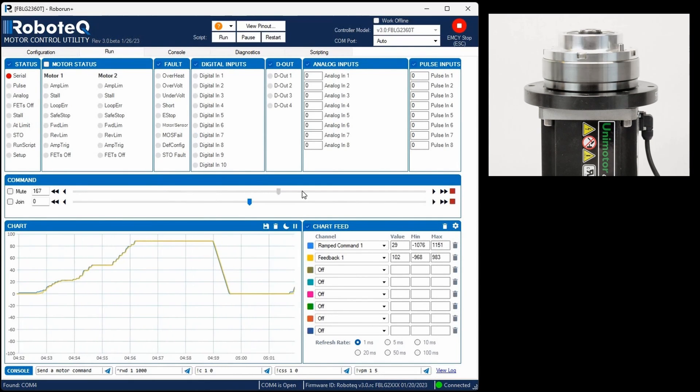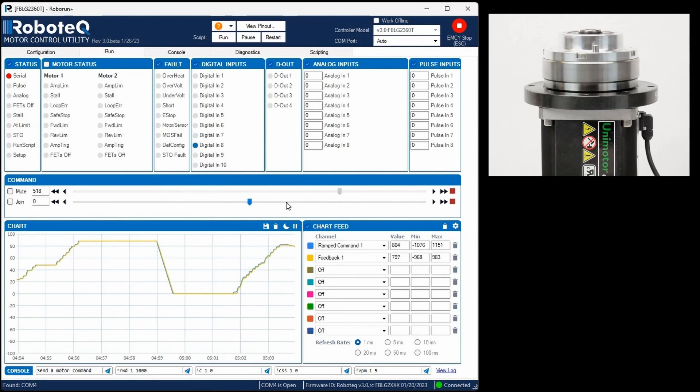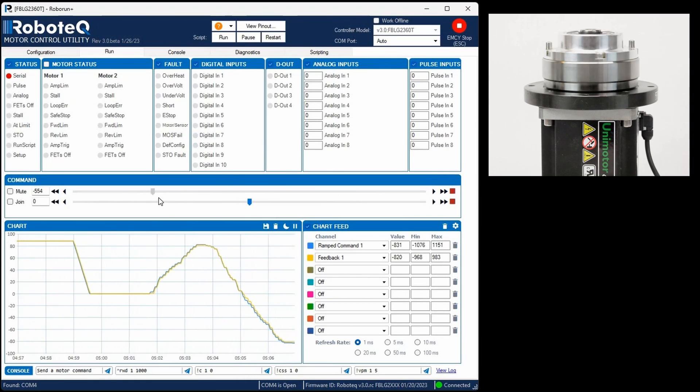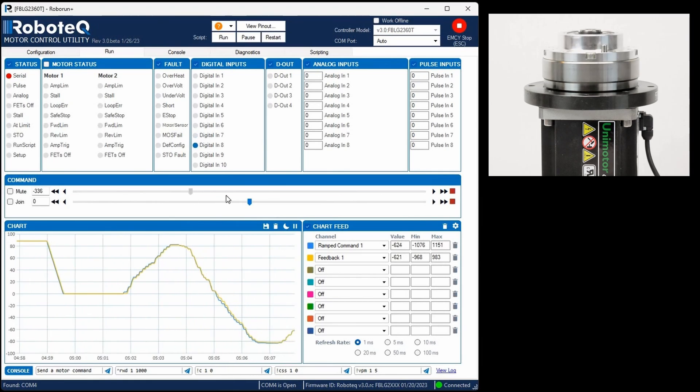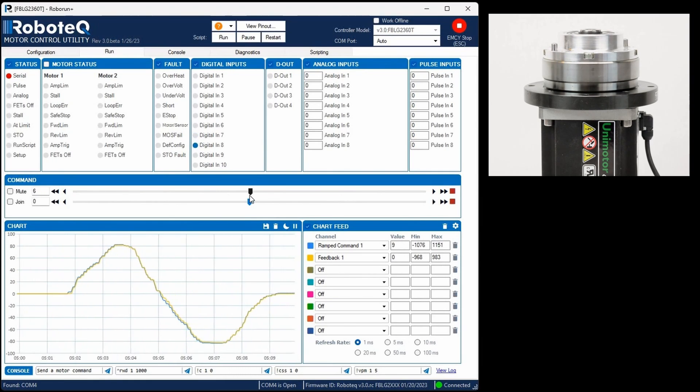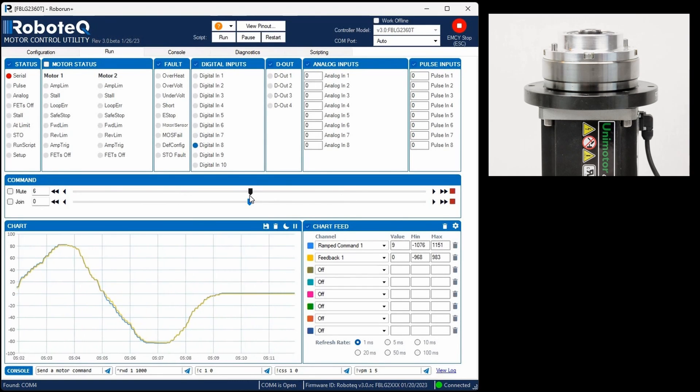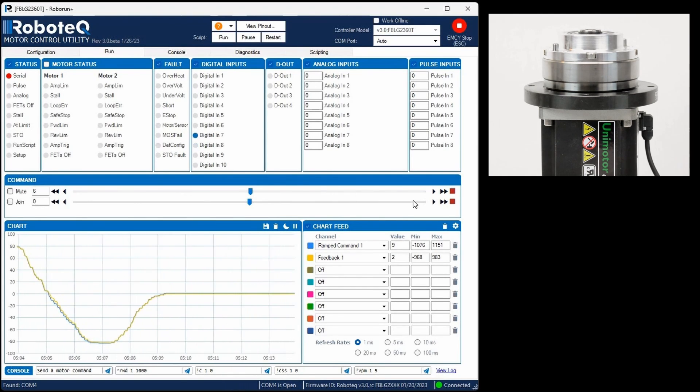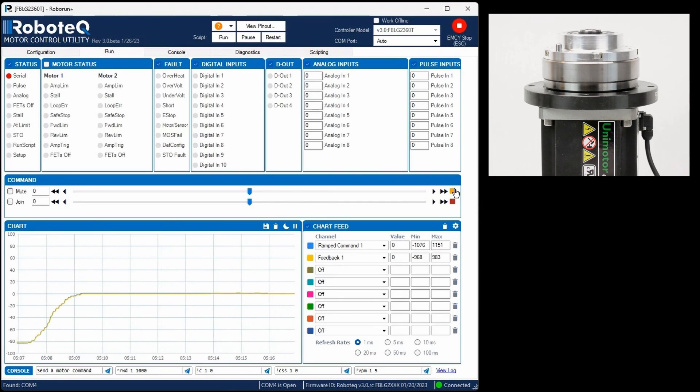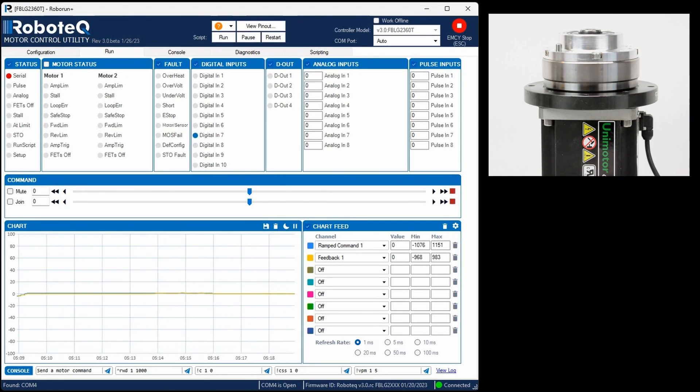Ideally, the ramped command and feedback values should coincide. If you observe this behavior when the motor operates without load, then the no-load speed mode configuration is successful. You can now proceed to our next video demonstrating the speed mode load tuning. Thanks for watching.